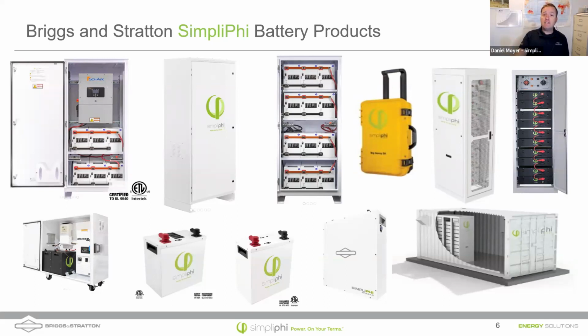On the far right is what I was just talking about, some of those rack-mounted systems. Each one of those modules in that far right picture is a 4.3 kilowatt-hour stack. I believe there are 10 in that stack, which would be 43 kilowatt hours. And if you look carefully at how those are wired, they're all wired in series. So instead of parallel, where we keep the voltage the same, with series we're increasing the voltage.